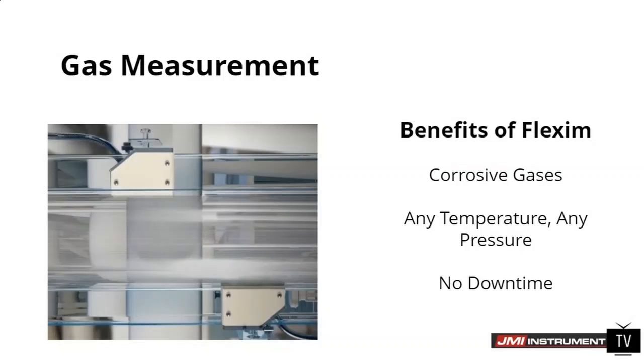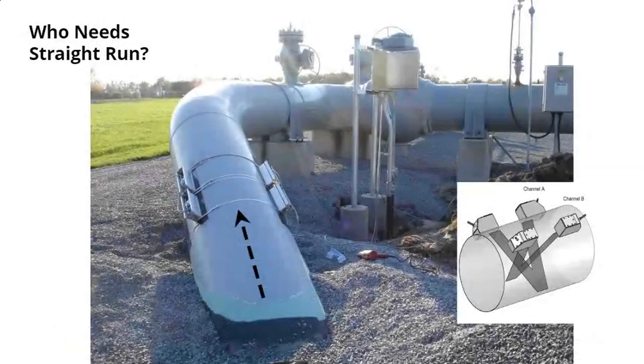Straight runs. So we have a couple different things that we do for straight runs. This is a typical application that we see a lot of, where the pipe comes out of the ground, runs a little bit, through a valve possibly, and then it goes right back in the ground. So we don't get a lot of straight run in some gas applications, especially storage fields.